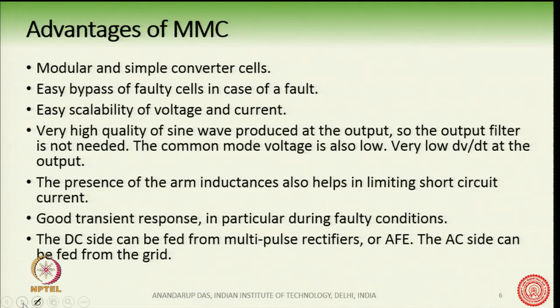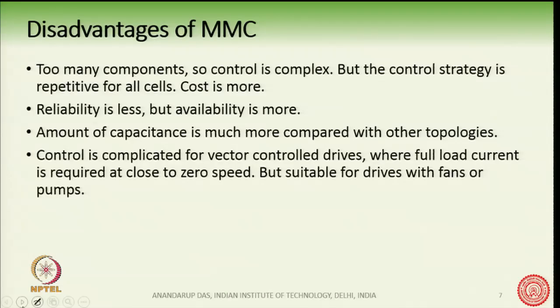MMC has good transient response during fault conditions. The DC side can also be fed from a multi-pulse rectifier for motor drive applications — for example, a 12-pulse rectifier providing DC input, with the MMC cells generating an AC output for the motor. Although MMC has many advantages, there are certain disadvantages: there are too many components, and the control is complex.